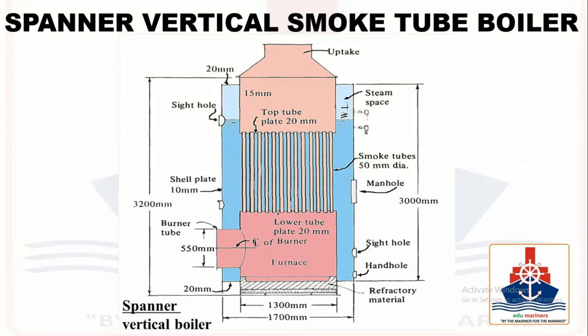It is claimed that these swirl flow tubes are more efficient than normal plain smoke tubes, in that they cause the gases passing through to swirl, coming into more contact with the tube wall and therefore increasing the rate of heat transfer.